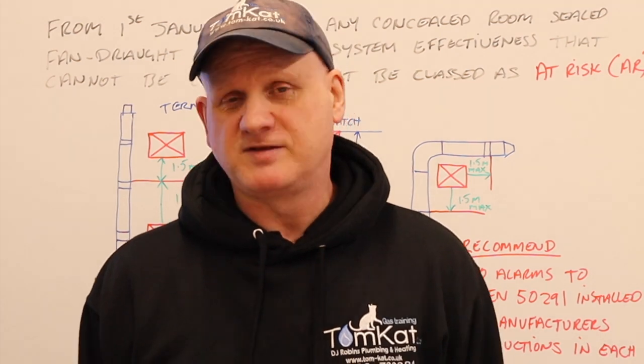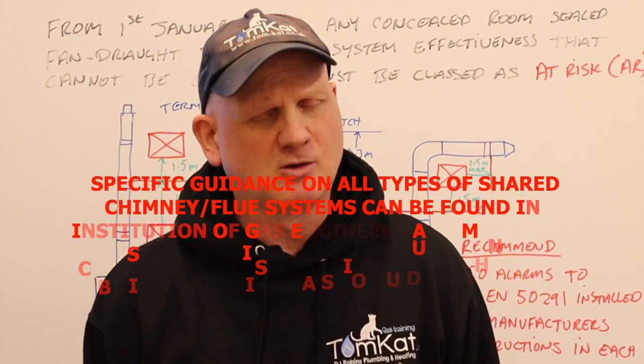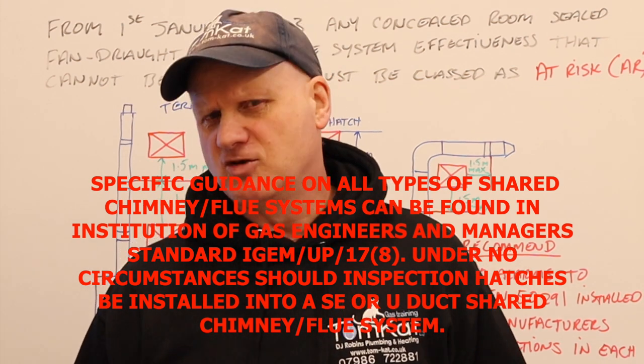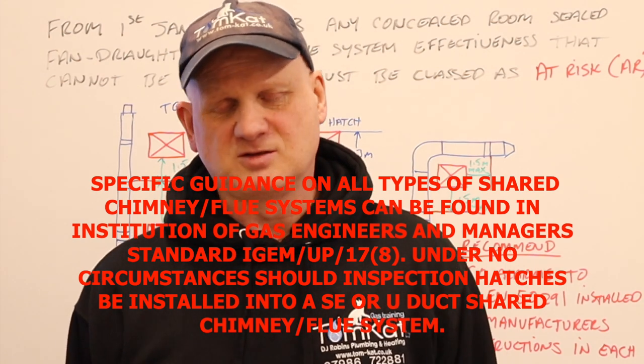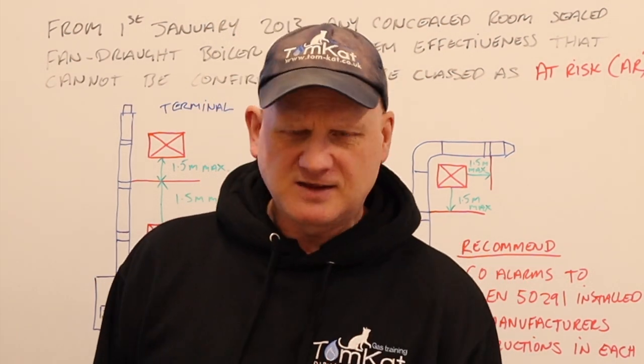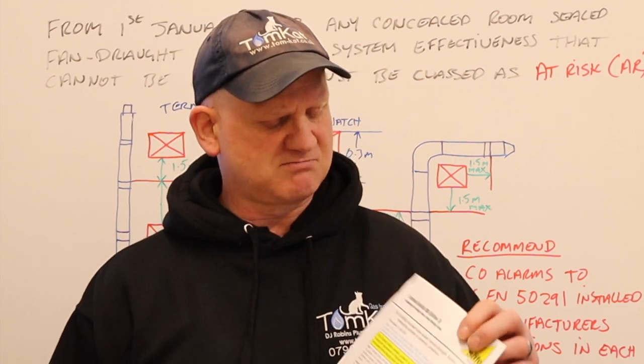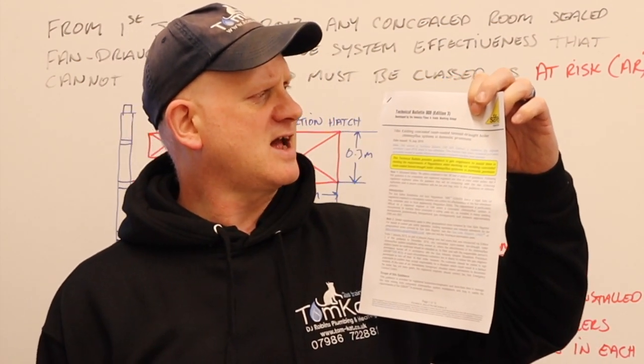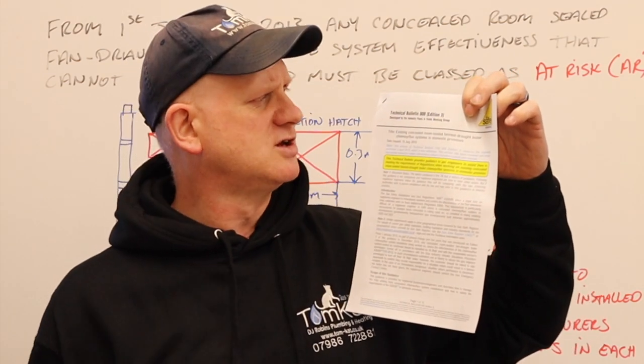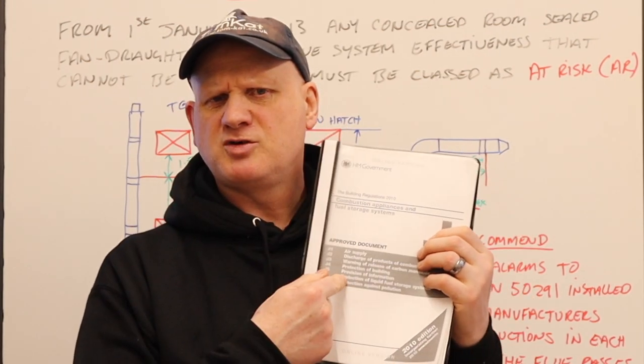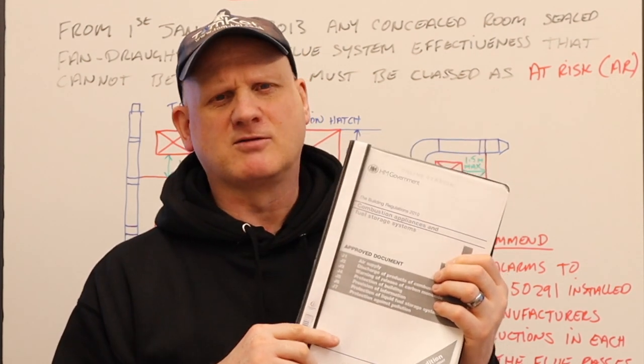In parts one and two of these videos, I'll put some links in the description below. We talked about SE ducts and U ducts — they don't come under flues in voids. But the new versions of flue systems, the communal flue systems or CFS flue systems, could come under flues in voids. The guidance can be found in the Gas Safe Technical Bulletin 008 Edition 3, as well as BS 5440 and Approved Document J, which will give us more information about flues in voids.